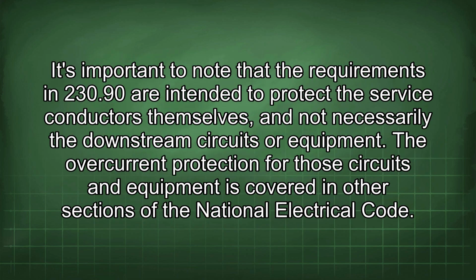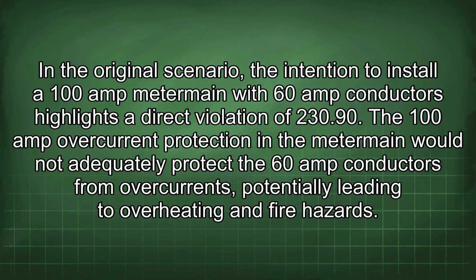It's important to note that the requirements in 230.90 are intended to protect the service conductors themselves and not necessarily the downstream circuits or equipment. The overcurrent protection for those circuits and equipment is covered in other sections of the National Electrical Code. In the original scenario, the intention to install a 100 amp meter main with 60 amp conductors highlights a direct violation of 230.90. The 100 amp overcurrent protection in the meter main would not adequately protect the 60 amp conductors from overcurrents, potentially leading to overheating and fire hazards.